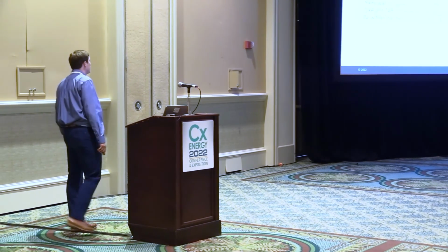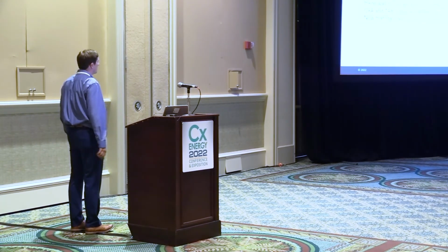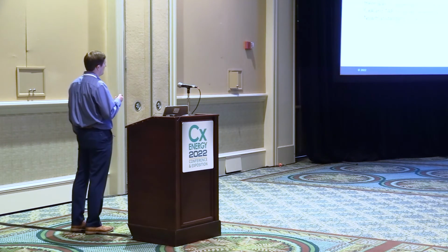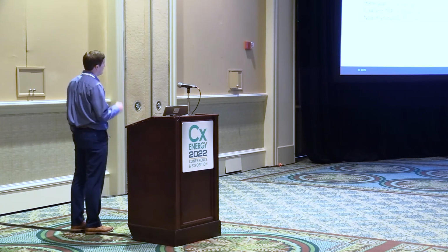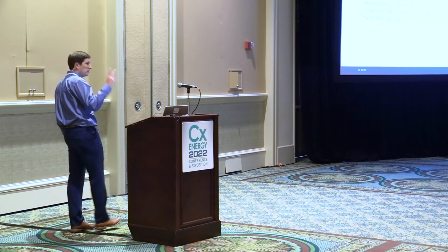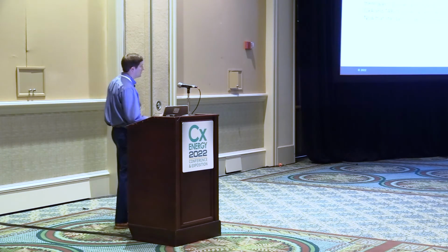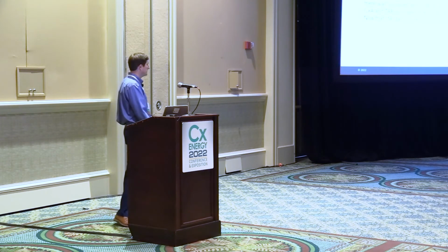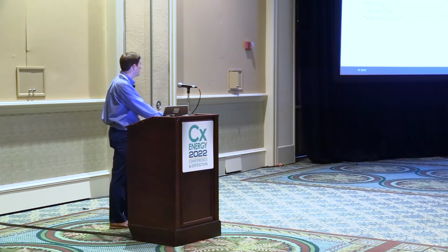So I'd say for me over at TAB, we got our CxA involved on unique issues. As I was talking about earlier with our fans in the corner, they were getting highlighted as problem fans, and we would have the mechanical contractor go back and check, and he'd say, no, this is set up right. We don't know what's wrong.